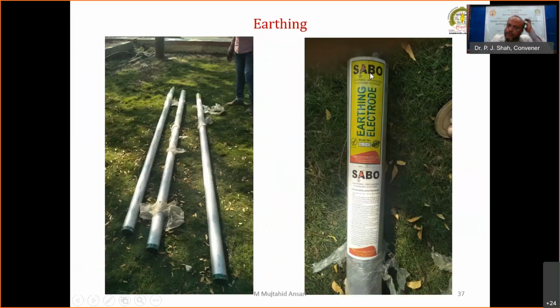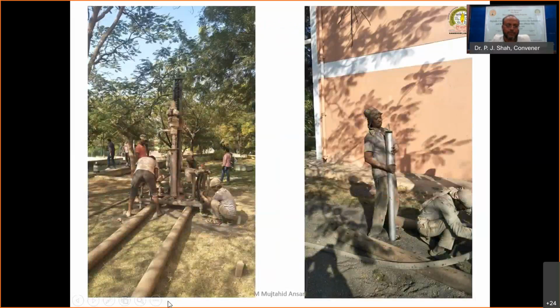It is a chemical earthing. So we have to do some borewell type excavations, and once the excavations are done, we have to immerse this one. The excavation is carried out with the help of borewell machines, and once the borewell is ready up to 10 or 11 feet, we immerse the earthing electrodes inside it. So there are a total of 6 earthing pits: 2 for ACDB or AC earthings, 2 for DCDB DC earthings, and 2 for the lightning arresters.